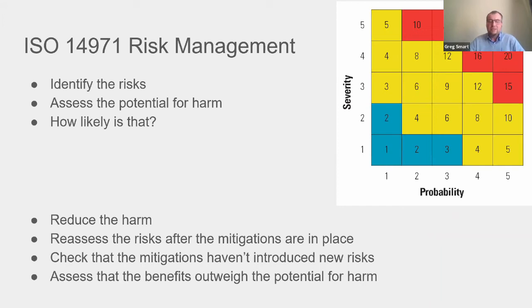The final step is to assess whether the benefits of your product outweigh the potential for harm. The regulations don't say that you have to remove the risk of harm altogether. They simply say that you must show that the benefit of your device being on the market is greater than any potential harm that may be caused.